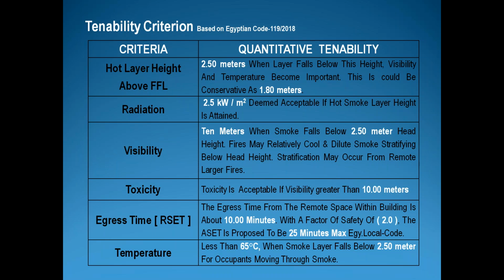The old people cannot sustain or stay aware if the temperature over them exceeds 50 or 60 degrees Celsius. So first we have 2.5 meters: when the smoke layer falls below this height, visibility and temperature become important. If the smoke comes lower than 2.5 meters, the visibility of the exit signs, the doors, or the egress elevators, if designed for that, could be poor.